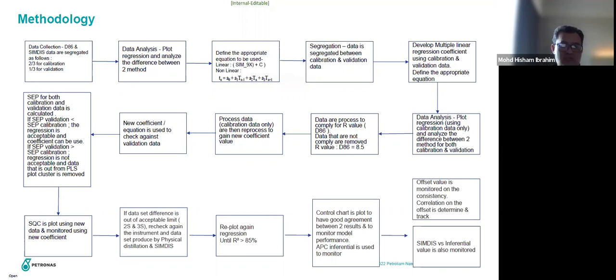After that, we plot the SQC using this new data and monitor using the new coefficient. If the data set difference is out of acceptable limits, such as 2 sigma or 3 sigma, we have to check the instrument again to see what the problem is. Normally it is because of calibration, and for physical distillation it is because of loss of sample components. After we find the data set difference exceeding the acceptable limit, we have to replot the regression until the R squared is more than 85%.